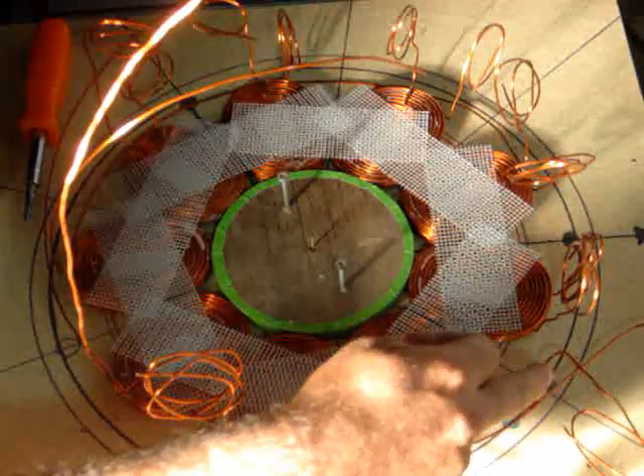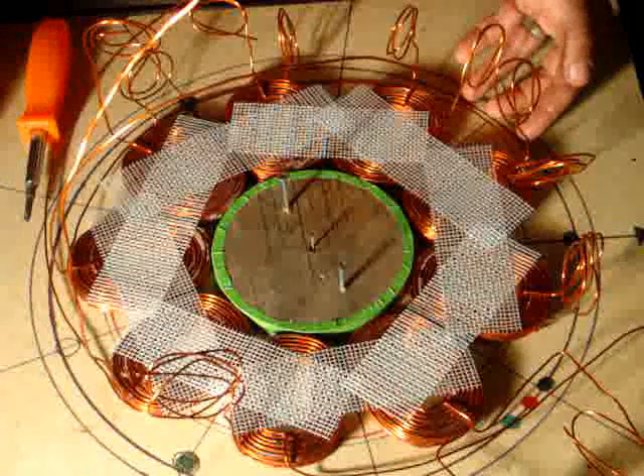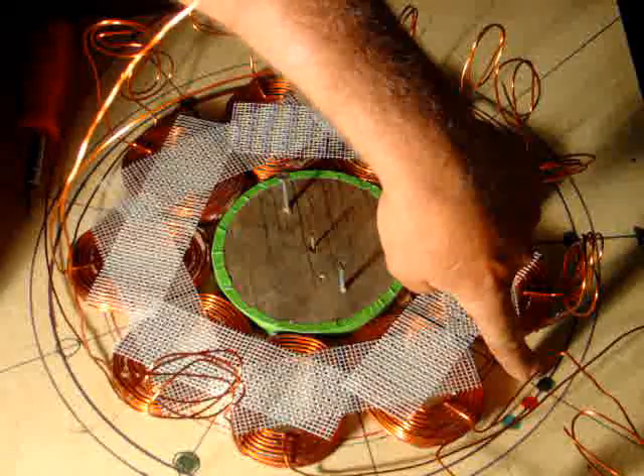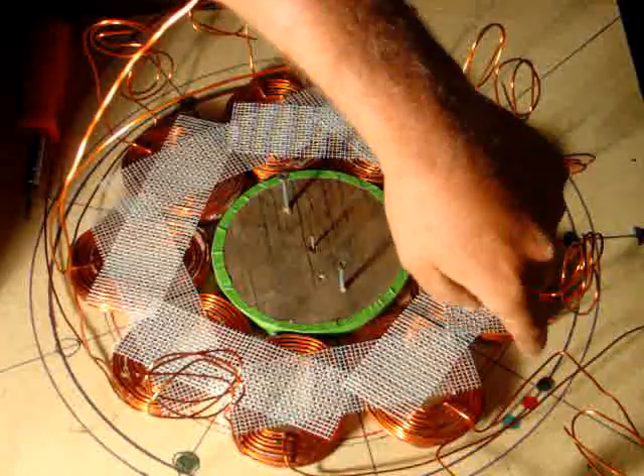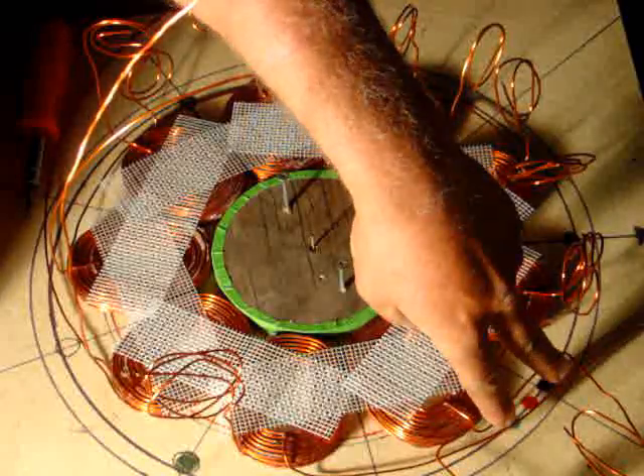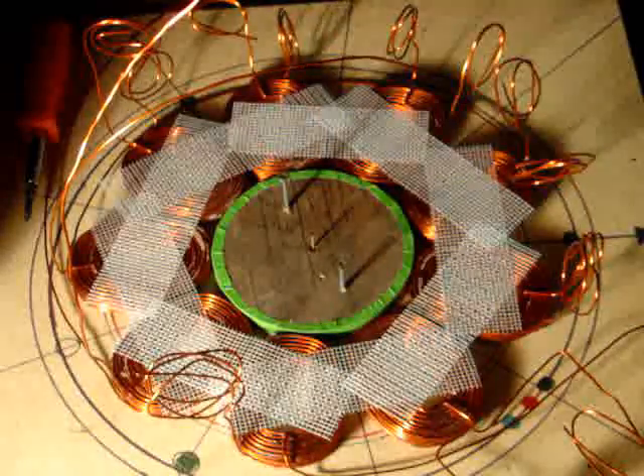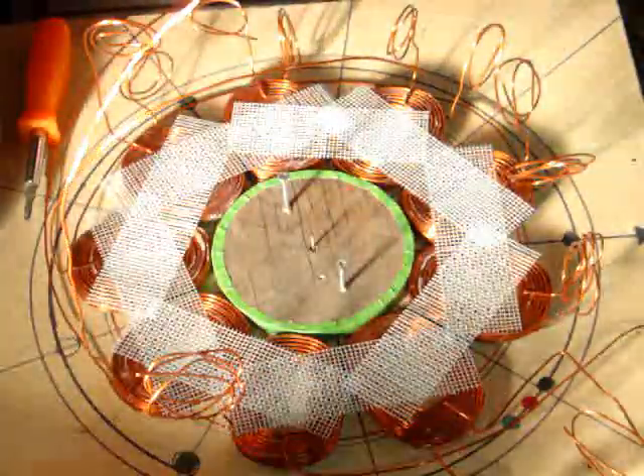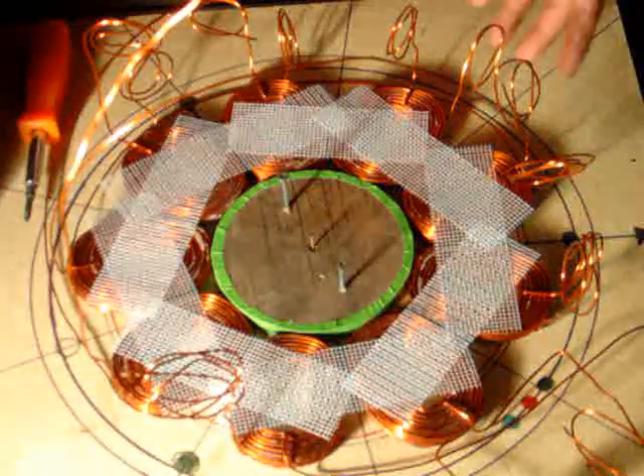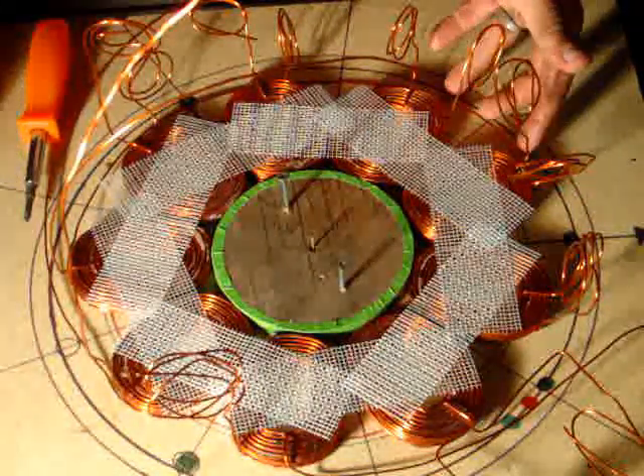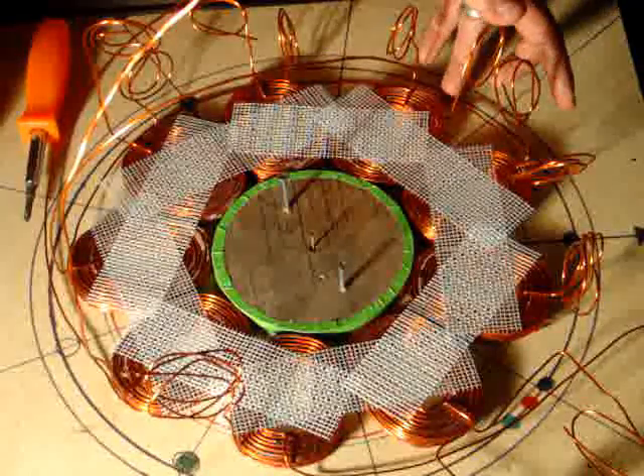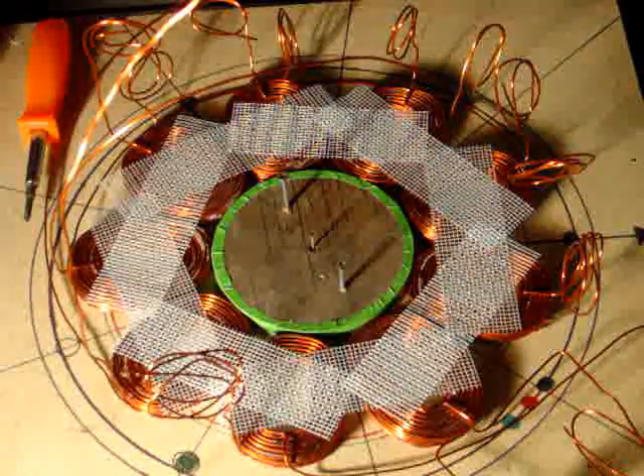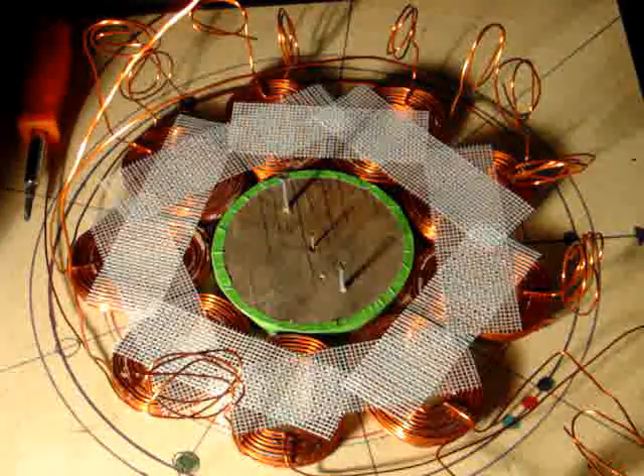This is going to be my starts and I'm going to put my finishes over here. Notice this is green, red, and blue. I didn't have a black that was actually working. So that'll be like first phase, second phase, and third phase. And I've got these close together where I can run a piece of wire across them and short these together. All your starts will be together because this is going to be wired in star. If I decide to wire this in delta later, all I've got to do is take that jumper off and I have all ends of all three of my phases. Over here I'm going to do the same thing, except I'm going to space them a little bit farther. And this is going to be phase one, phase two, and phase three right here. So I'll have three phase output in star. And then I can wire off. I'll explain star and delta wiring a little later on.